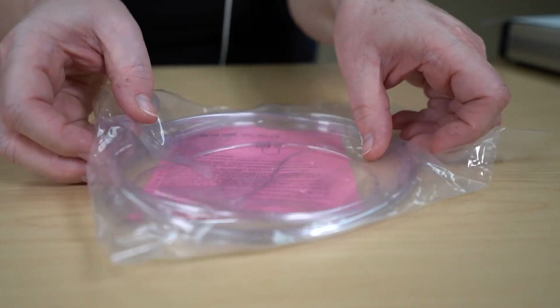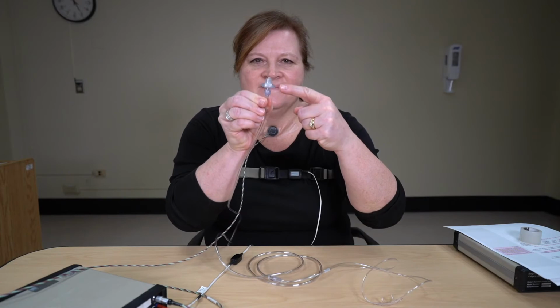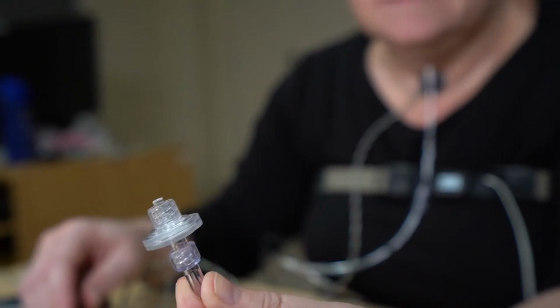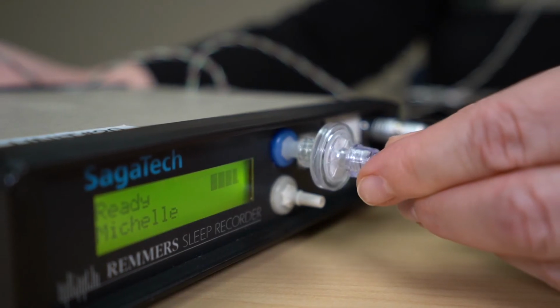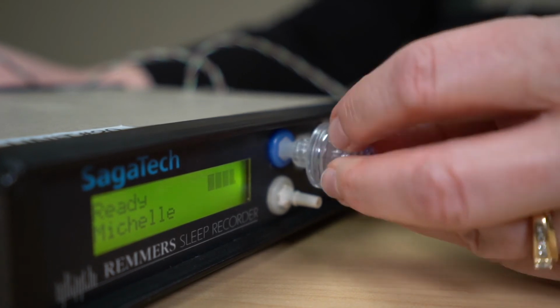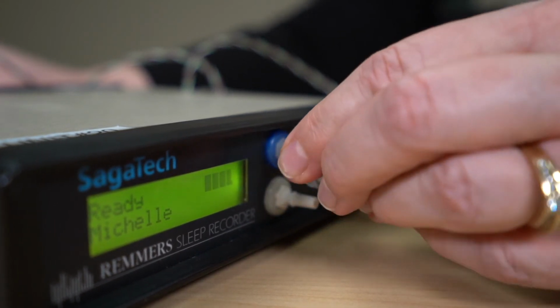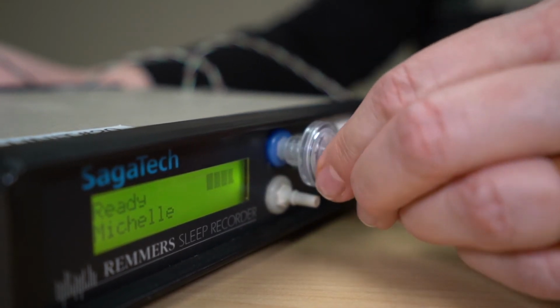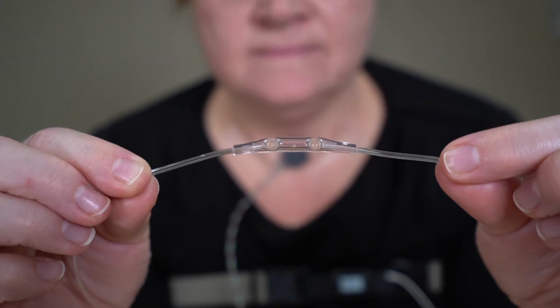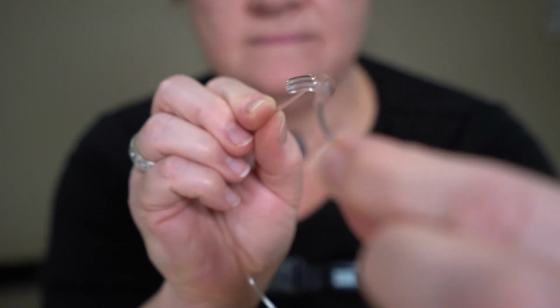The next accessory is the nasal cannula. To attach the nasal cannula to the recorder, you will connect the filter end of the cannula to the port with a blue ring around it and turn clockwise about 2 or 3 times until tight. To attach the cannula to yourself, place the prongs in your nose with a slight curve pointing back and down.